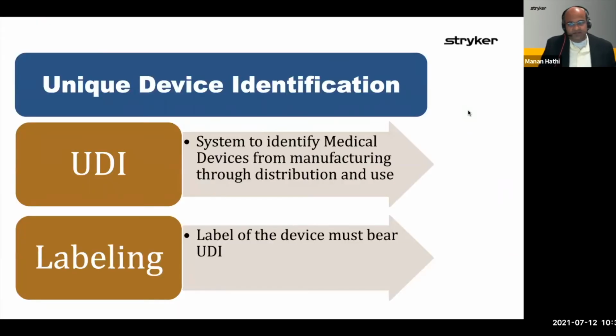So what is UDI? Let's start with the basics. My colleagues gave an excellent presentation on the technologies used in automatic device identification. However, when you look at the regulatory aspect, and at the current state of medical device technology in the absence of UDI, you see many challenges with traceability and tracking of medical devices, because each device is given its own catalog number by its parent company, and they have their own identification systems that, when taken together, are anything but unique.